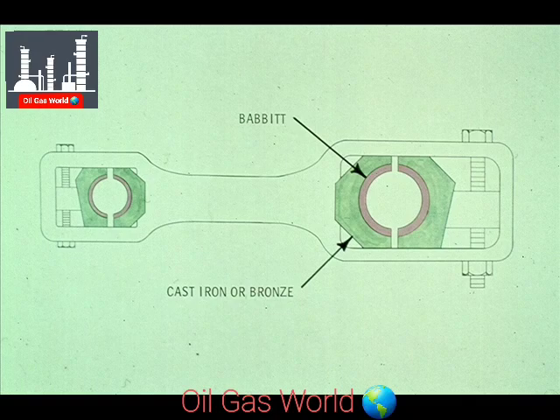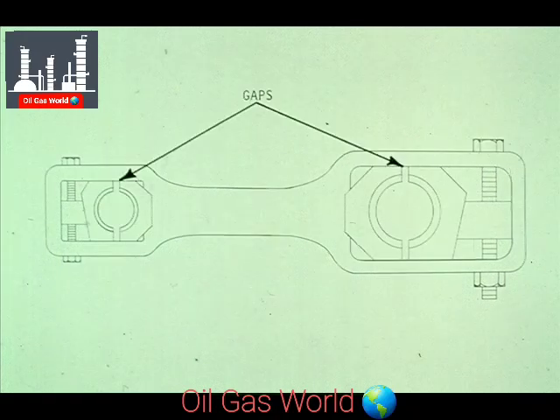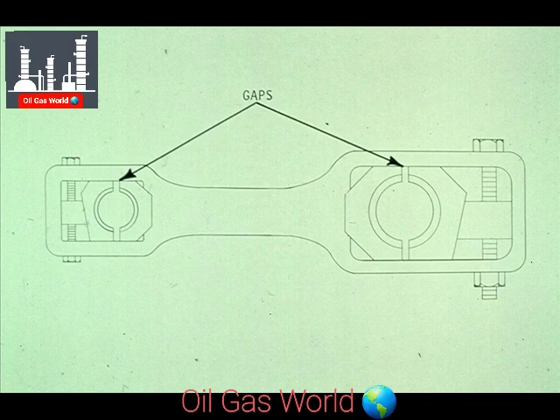These bearings are made of cast iron or bronze, and lined with babbitt. By looking closely, you'll see that there are gaps between the halves of each of the sleeve bearings. These gaps are to allow the bearing halves to be brought together when adjusting for wear.